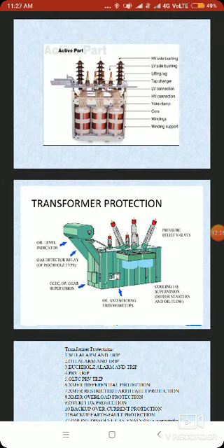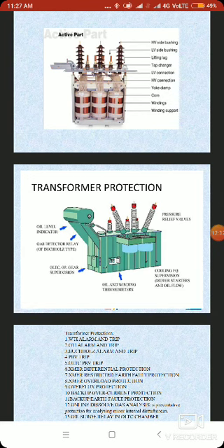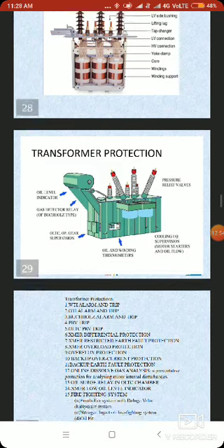And then we have this thing, OLTC, the on-load tap changer. Operating gear supervision, there is a box connected. Then oil and winding thermometers. Then this is the cooling part, that is the control fans, control cooling, supervisory motor starters, and oil flow. Whatever control box we have is mounted in front. And at the top we have got the pressure release valve.